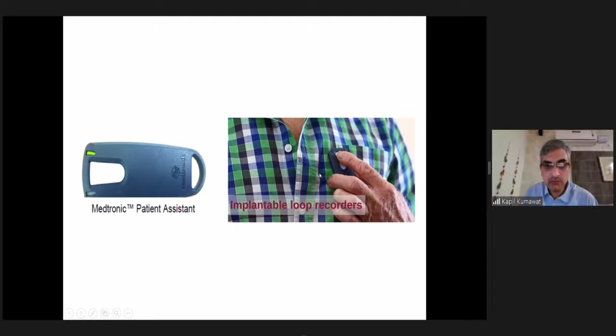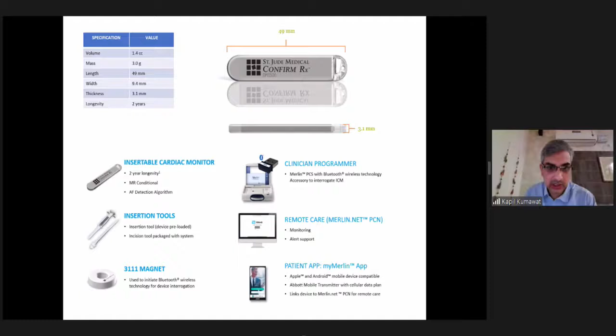So after giving local anesthesia, you insert the insertion tool into the subcutaneous tissue and inject the device, which is kept inside the insertion tool, just like a plunger. Then you program it using the usual programmer, and pair this device with the patient's mobile through Bluetooth. Then it can be available on Abbott's Merlin.net and can continuously transmit data, or transmit data whenever the patient wants, or at a particular pre-programmed time.